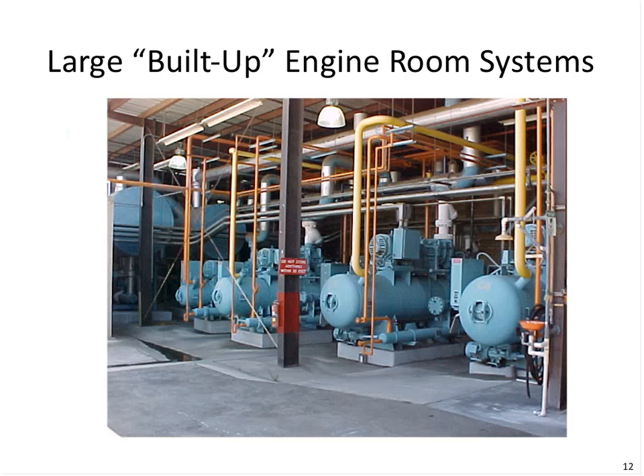And then here's a picture of a large built-up engine room where we have individual compressors. You can see the size of that really prevents skid mounting. There's numerous vessels for holding the refrigerant, typically being ammonia, although carbon dioxide is coming into play in some of these systems. And even here we can see different size compressors for staging, and that would be based on what level of product cooling or storage that we might have. Now, these larger built-up systems usually are the most efficient or have the opportunity to become that way. There's unlimited tonnage, life of the equipment. Some of this equipment gets to be 50, 60 years old, still operating, can be rebuilt.